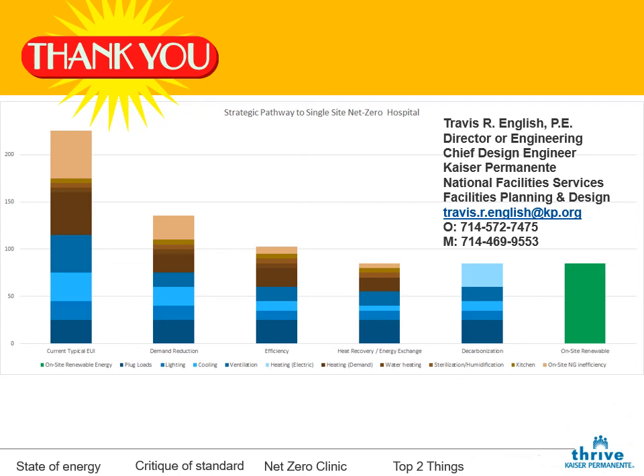I showed you data earlier from that research project that we did in Long Beach, where we collected the air quality data at the different air change rates. Well, we had a nice big failure in the middle of that project. You always learn from failures. Failures are the best, right? The design engineer and I were on the phone, and I remember talking to him. We said, hey, we'll program all the patient rooms to let them go down to 2 air changes per hour, but they probably won't all go there at once. You know, we'll have some diversity. Some will go to 6 air changes, some will drop to 4 air changes, that kind of thing. And we were totally wrong.